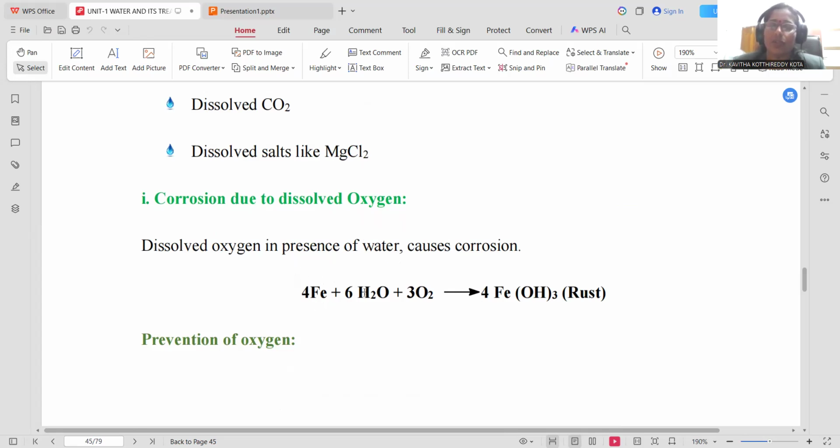That iron is already in combination with water, which contains oxygen as dissolved oxygen. Whenever these three components are mixed together in the stoichiometric ratio, there is formation of ferric oxide, which is called rust. Rust induces failure of the boiler body, and corrosion of the boiler is possible.